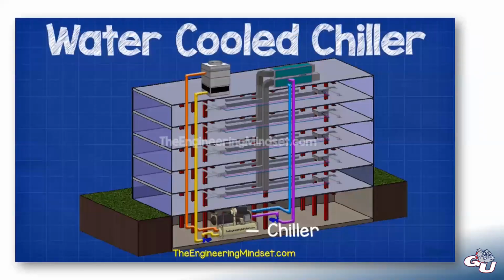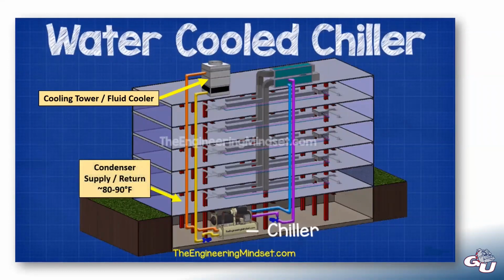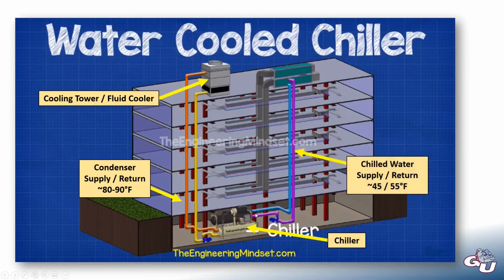At a more macro level, this is essentially what this would look like. We have our cooling tower or fluid cooler up on the roof somewhere. The orange and yellow pipes here would represent our condenser supply and return. In this case, the chiller's down in the basement, but you can see on this side we have condenser water piping. On this side we have chilled water piping, and so the heat transfer would be going from one stream to the other. And then we have chilled water supply going up to some air handlers with chilled water coils.